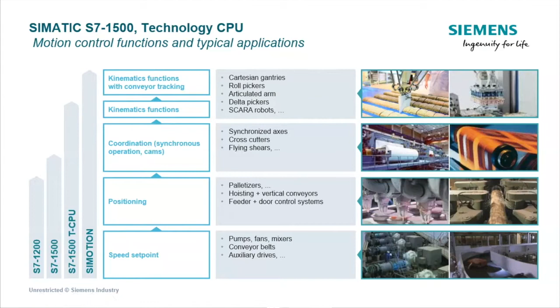So you have the S7-1200, capable of speed set points and basic positioning. The S7-1500 can get into some minor coordination, but when you really want advanced motion control, that's when you use the 1500T to get kinematic functions, absolute gearing, and camming.